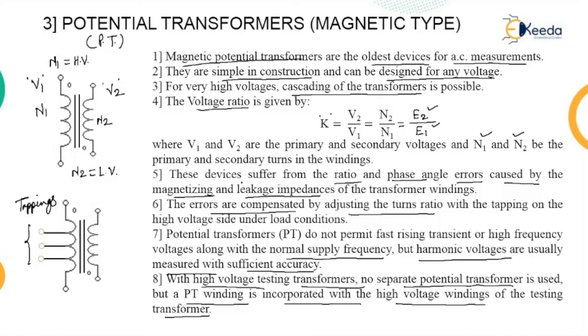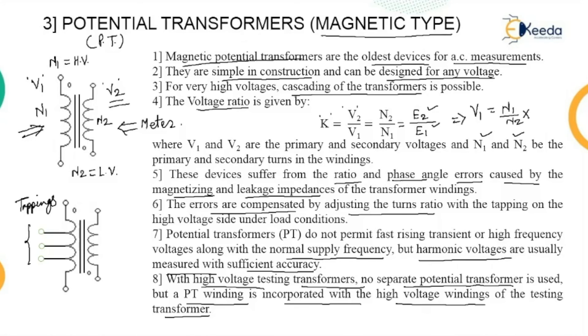This is the magnetic type potential transformer. The high voltage side is the primary side, and the metering side is the secondary side. The meter placed on the secondary measures voltage v2. The actual high voltage v1 is then calculated as: v1 = (n1/n2) × v2, where v2 is the meter-measured voltage and n1, n2 are the known number of turns of the primary and secondary windings.